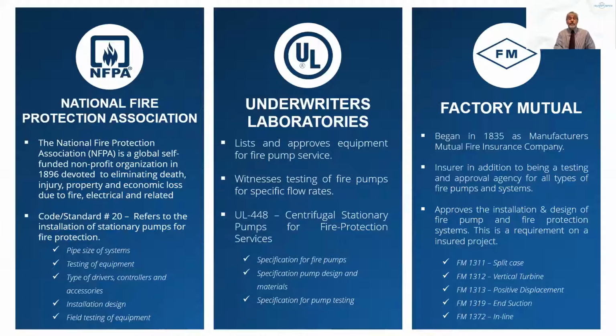Now, this is fairly important when it comes to the oil and gas industries, because you guys at the EPCs and consultants will send us various specifications to comply with. But we cannot deviate from the UL and FM standards and still maintain our listed status. So under these circumstances, we can only offer you equipment that would be UL FM if it were not for the requirements of your specifications. So there'd be caveats on that.